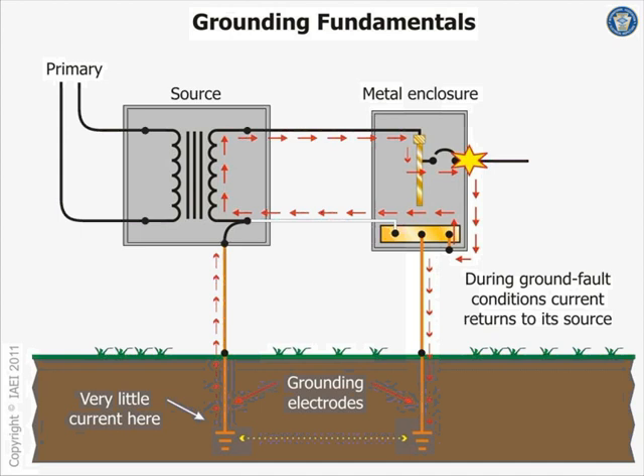I work with low voltage. I install fire alarms. Okay. And it's power limited. Most of the fire alarms have a grounding conductor that goes directly to the main panel. But it caught my attention that for some applications, like when we wire to an outdoor device like a post indicator valve or fire sprinkler system, now we are required to install a surge protector, a diplex surge protector.